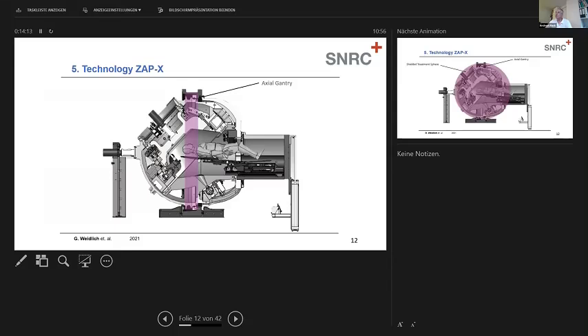You see that everything is attached to a so-called gantry, a ring. You see the imaging system, which is mounted inside the inner sphere. So it's an X-ray system which controls via live images and compares these live images to the pre-taken CTs, the DRRs. And if there is any deviation, the table will correct for this.